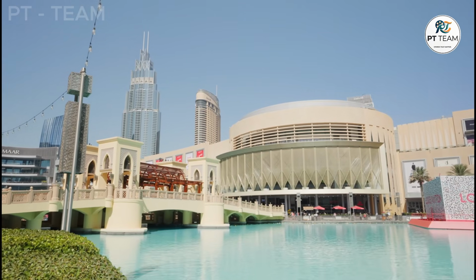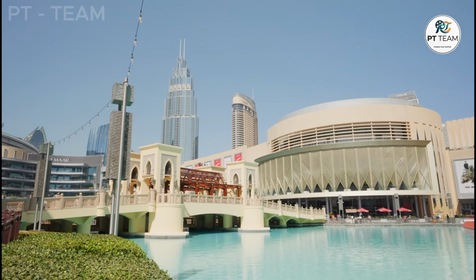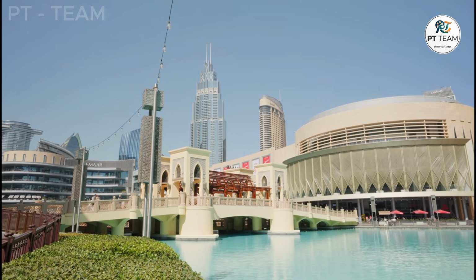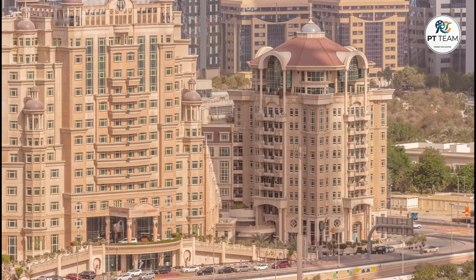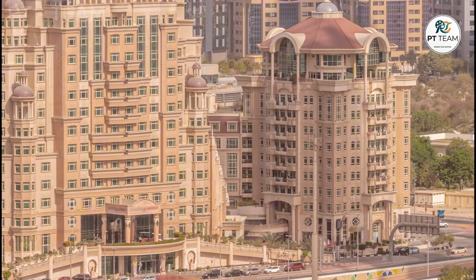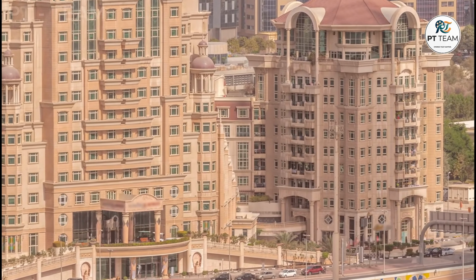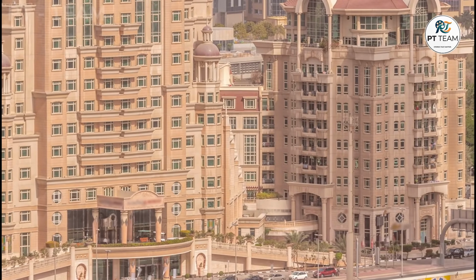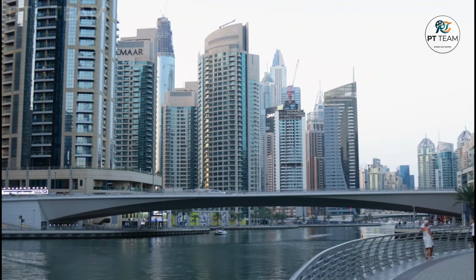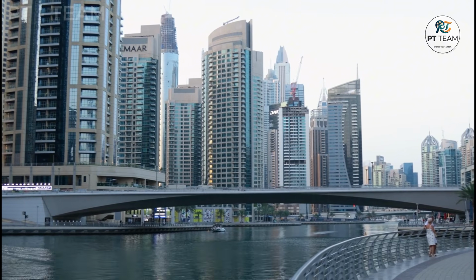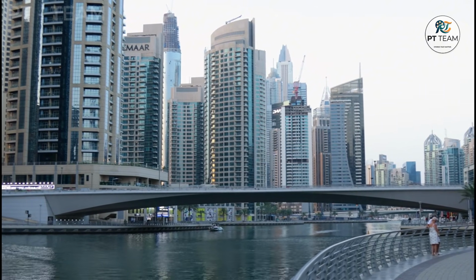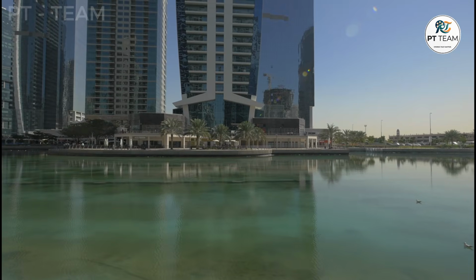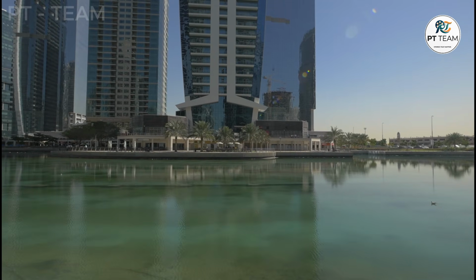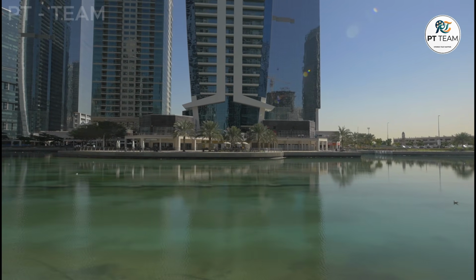Follow the water from its origin point. Wastewater leaves a building and enters the municipal sewer network. It travels to a heavy treatment facility, undergoing intensive processing and rigorous quality control to meet cooling standards. The treated water is then pumped through a dedicated distribution network directly to the cooling plants, where it is exposed to air in cooling towers to facilitate evaporative heat rejection.